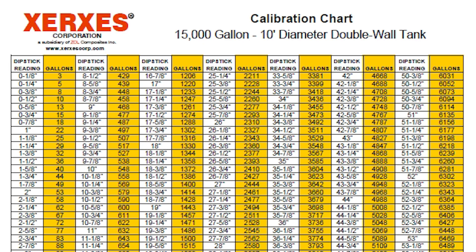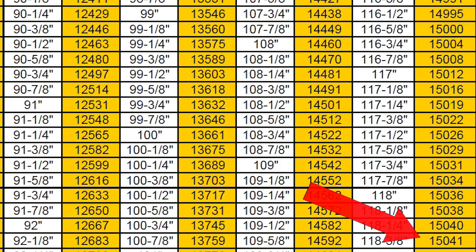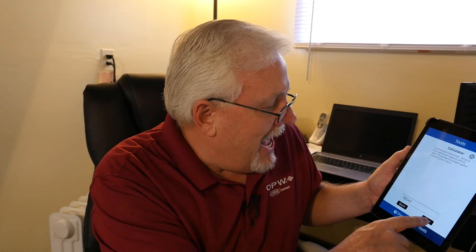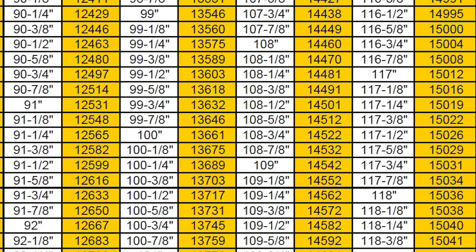Look at your tank chart and the very last value — second page, third page, whatever you've got — will be the final value, which for us is 15,041. That's what I'm going to enter: 15,041. That is my full tank — completely full — not taking any percentages into consideration, just the full value, whatever the maximum number is on that chart. Then it asks for the inch reading. It's very important that you start learning to convert your fractions to decimals, because we need two decimal places.